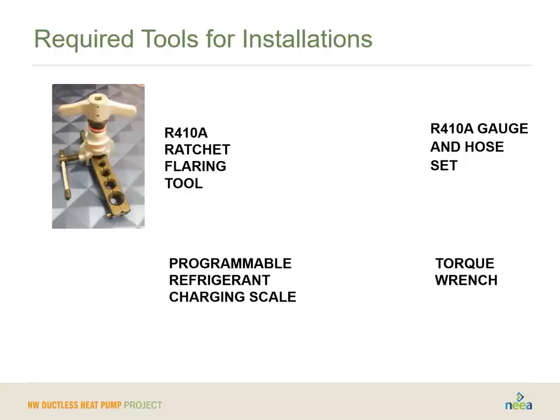The first, you want an R410A ratchet flaring tool. And the reason why is that the flares that come factory designed from the manufacturer are really designed just to keep the thing together as it's being shipped. They're really not ideal for the rigor that will be necessary once these systems are fully charged. So you're going to want to create a new flare so you have excellent connections.